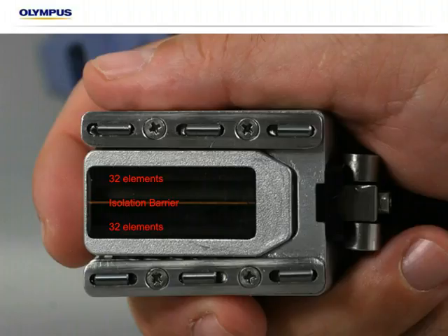See a few other things here. We have some carbide skates in order to preserve the probe, and the same adjustment system as the RexoFORM, which allows us to put it on the pipe surface or other curved surface, push down, and then lock it into place at the right height to adhere to different curvatures.